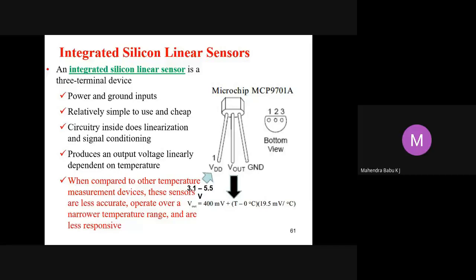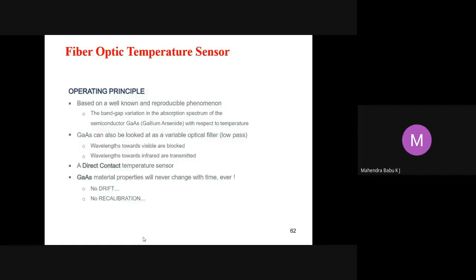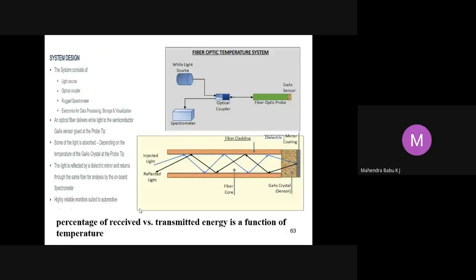We have another type of temperature sensor called fiber optic temperature sensors. The operating principle is based on a well-known and reproducible phenomenon, the band gap variation in the absorption spectrum of the semiconductor gallium arsenide with respect to temperature. This gallium arsenide can also be looked at as a variable optical filter. Wavelengths towards visible are blocked, wavelengths towards infrared are transmitted. It is a direct contact temperature sensor which has no drift and no recalibration. And the system consists of a light source, an optical coupler, and a spectrometer.